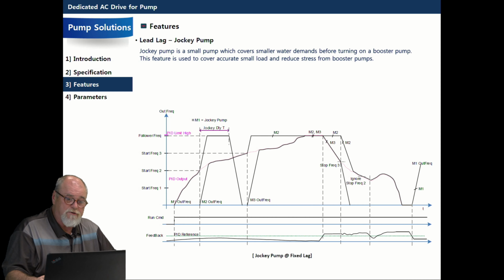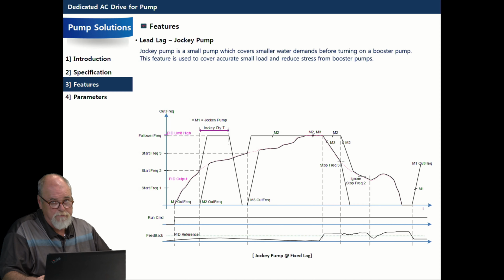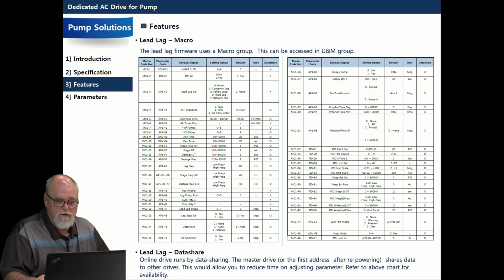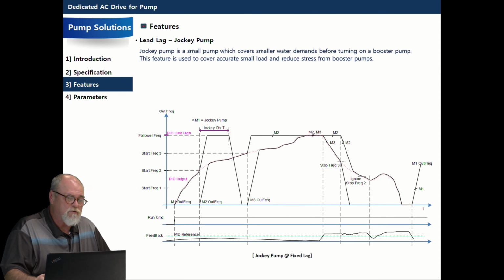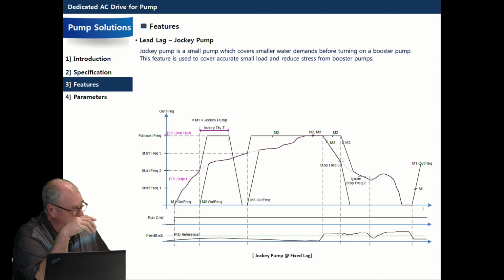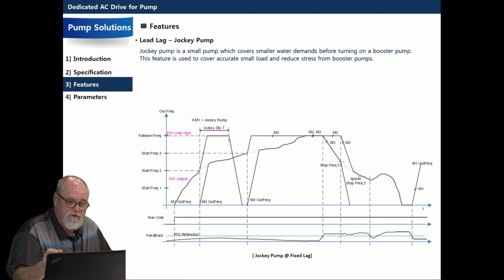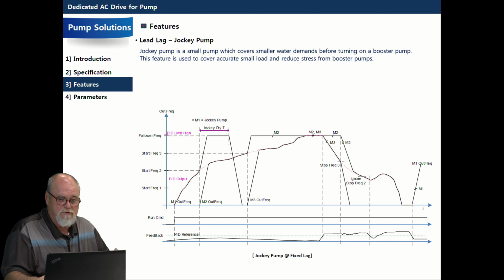We also have the ability to control small jockey pumps in a system with 2 large VFDs. If you had 2 large VFDs but didn't require a third, a jockey pump would handle smaller flows when required. We can also daisy chain that and program one of these to act as a booster pump.